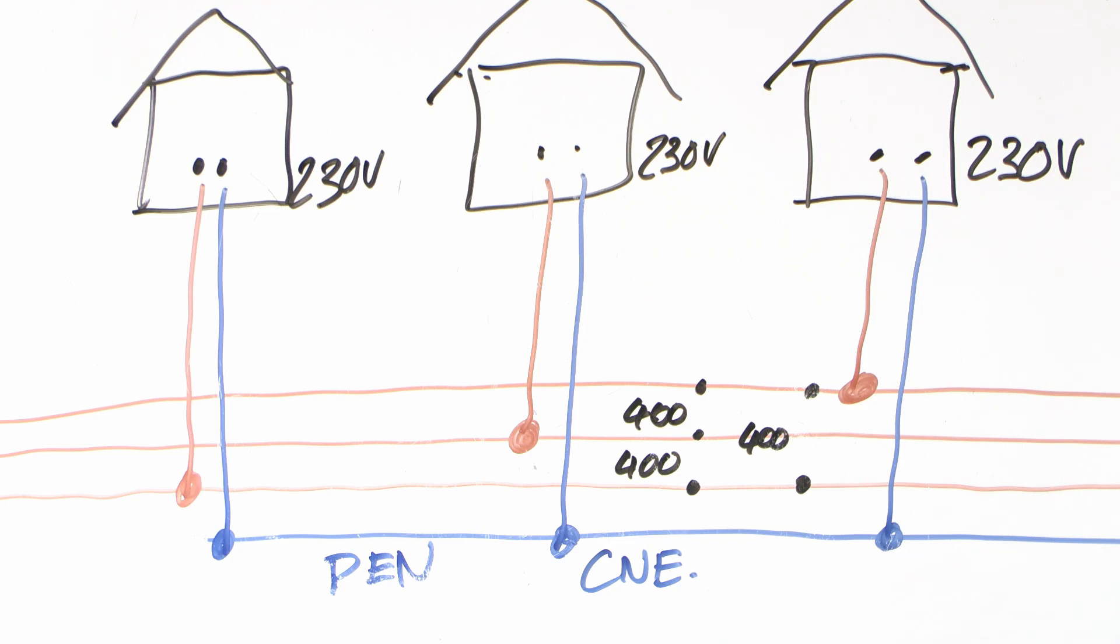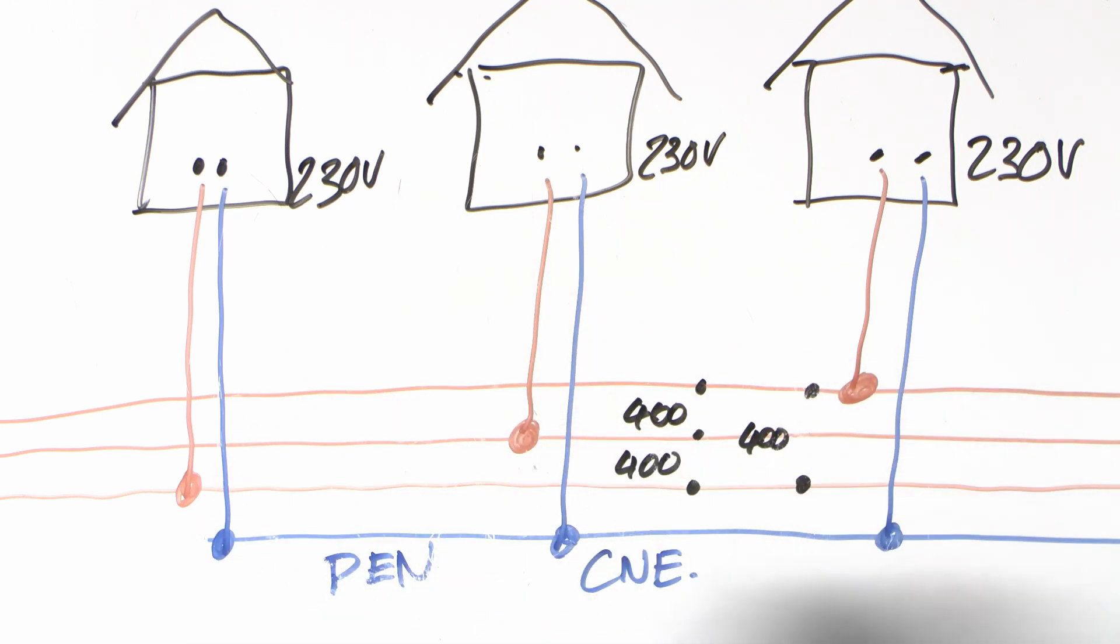However, what goes wrong is when this is broken and then the load in each of these properties is different, which in a situation like this is going to be inevitable because it's desperately unlikely that every single house is going to have the exact same load turned on all the time at the same time. And what then happens is that if the load in one increases and one obviously goes away, this conductor does not stay at the same potential relative to the others. It tends to get pulled in whichever direction the loads actually are. And the more unbalanced the loads are, the worse this situation gets.